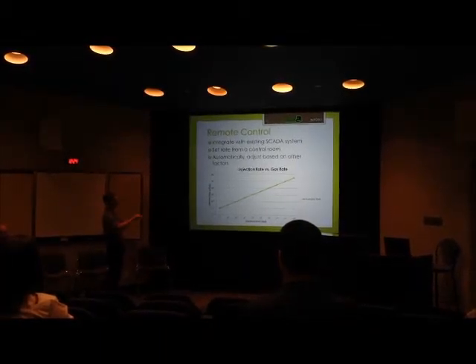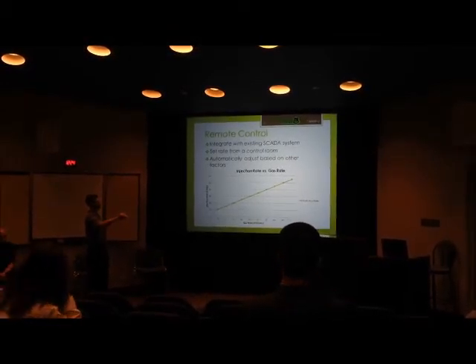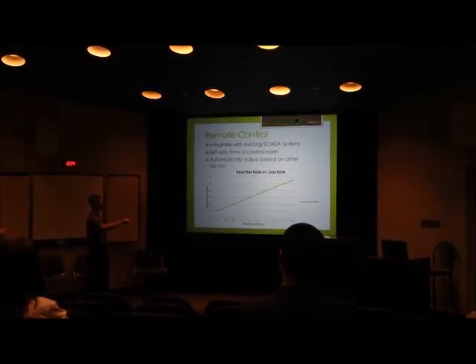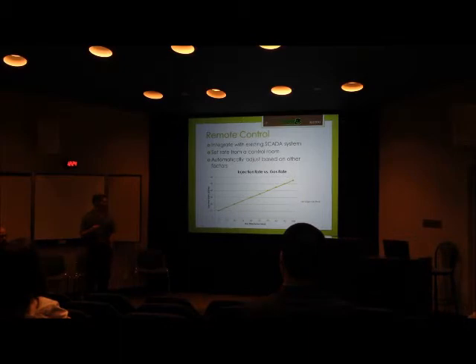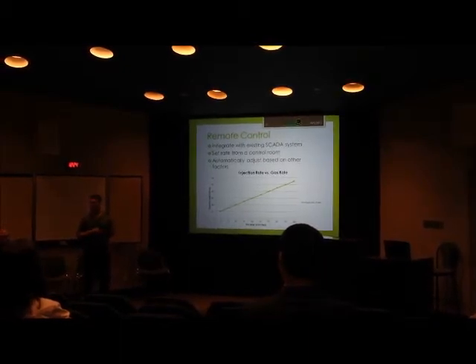So say this is a corrosion inhibitor off of a compressor station. Both compressors are running, you're doing 100 decks of gas, you want 55 liters of corrosion inhibitor. One compressor goes down, you're saying, okay, well, at 50 decks I only need 30 liters. But do you think when that one compressor goes down, that's the first thing on the operator's mind is to go trim back that chemical?